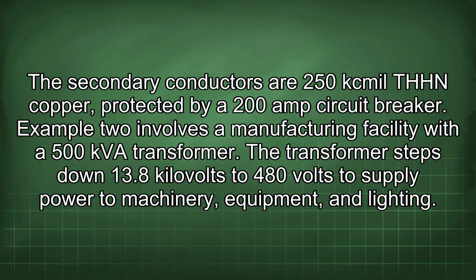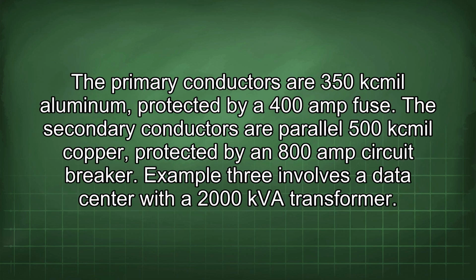Example 2 involves a manufacturing facility with a 500 kVA transformer. The transformer steps down 13.8 kV to 480 volts to supply power to machinery, equipment, and lighting. The primary conductors are 350 kcmil aluminum, protected by a 400 amp fuse. The secondary conductors are parallel 500 kcmil copper, protected by an 800 amp circuit breaker.